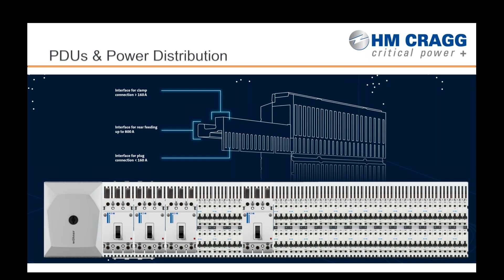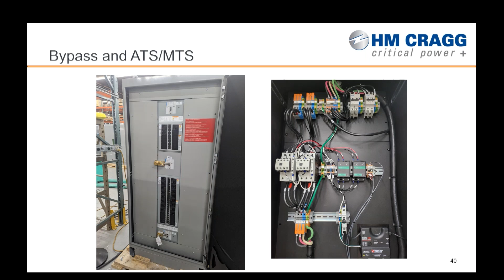Bypass, automatic transfer switch, manual transfer switch - again, this is an opportunity to go a little lower quantity, more unique type projects. We have a bypass system here with Kirk key interlocks, and on the right side, a custom automatic transfer switch which we utilized on the front end of a UPS system we built.